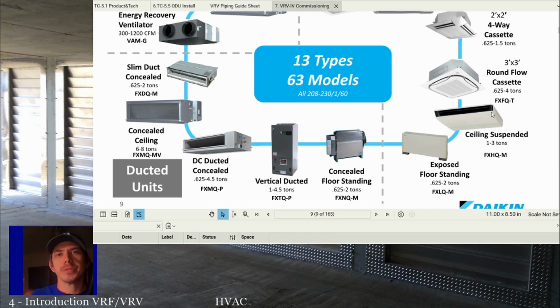Ceiling suspended units, you don't see these a ton, but you do see them installed now and then in bigger rooms where you want to blow air across the top of a room. This is generally going to be mounted just below the ceiling, but you have a horizontal discharge air instead of a vertical like the ceiling cassettes. Floor standing is a good replacement for radiator style units or water source heat pumps that go along a wall. That's where you'll see these used a lot. Concealed floor standing is the same thing. It's just you make your own outside cover for it so you can make it look different than the standard model.